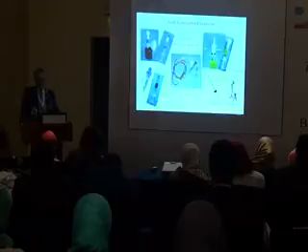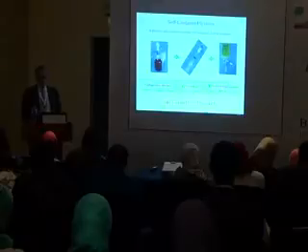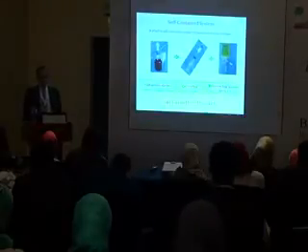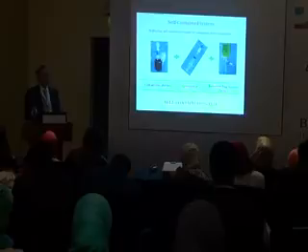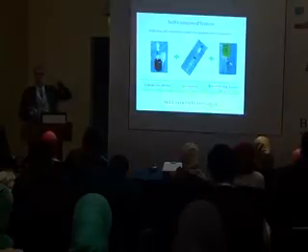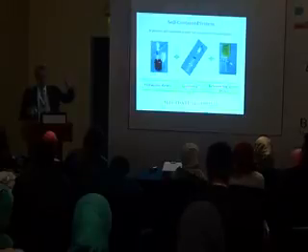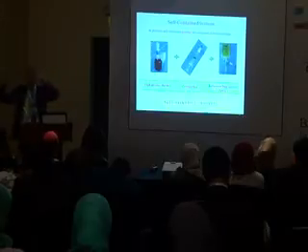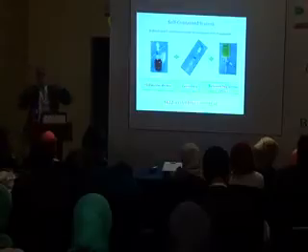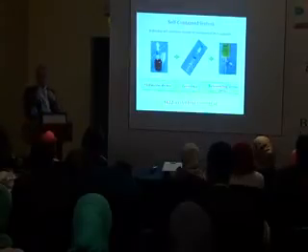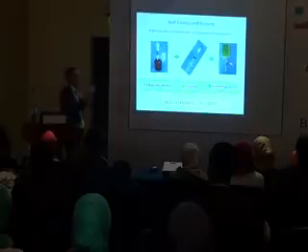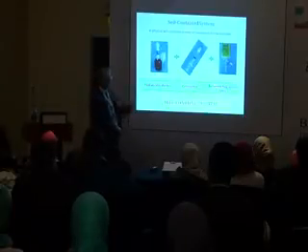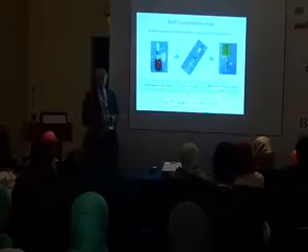We have self-containing systems from different companies, and this means in practice the self-containing system was composed with other solutions. If you have a self-containing system from company A, then you need the device from company A to bring it into the infusion solution from company A — there is no interoperability.